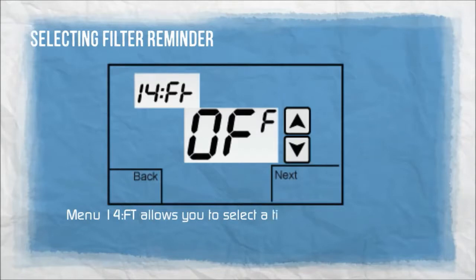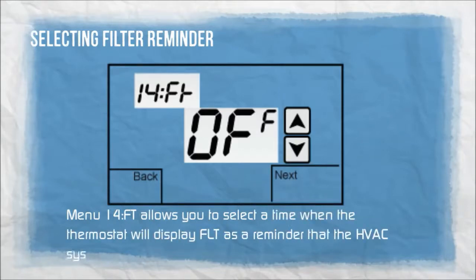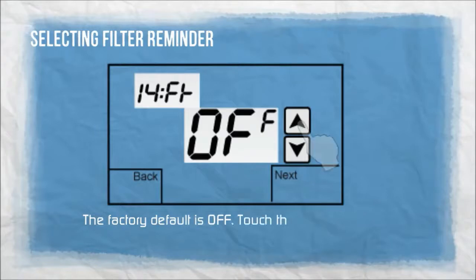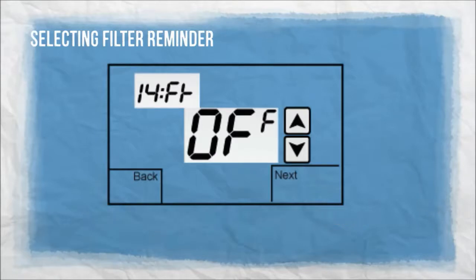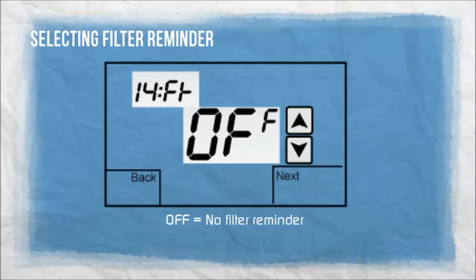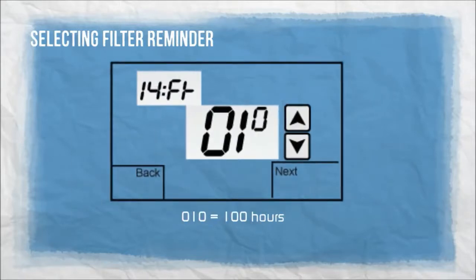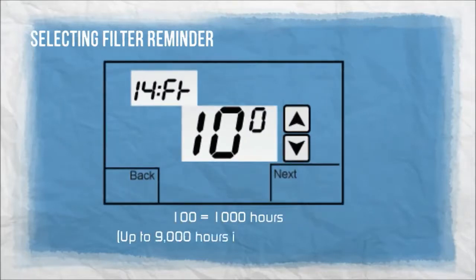Menu 14FT allows you to select a time when the thermostat will display FLT as a reminder that the HVAC system filter or filters should be replaced. The factory default is off. Touch the up or down arrows to set the filter reminder. Off: no filter reminder. 010: one hundred hours. 100: one thousand hours, up to nine thousand hours in one hundred hour steps.